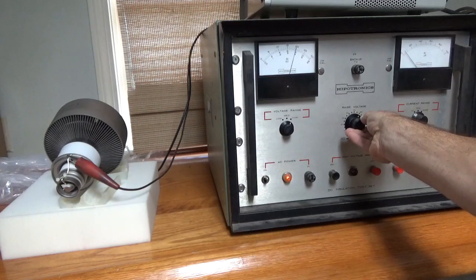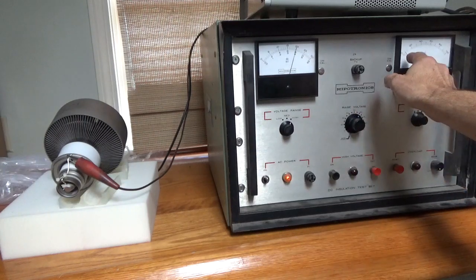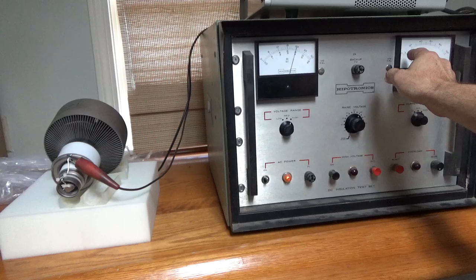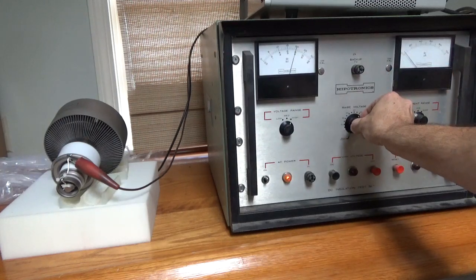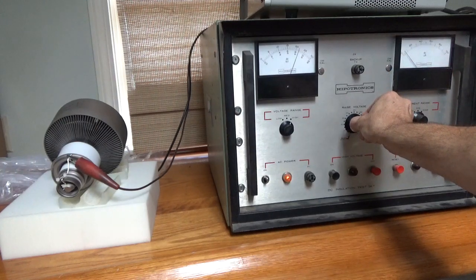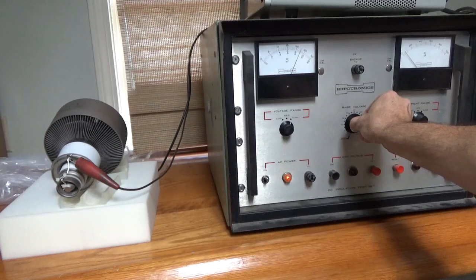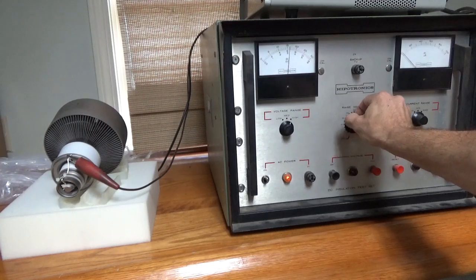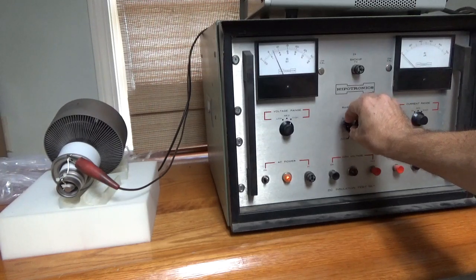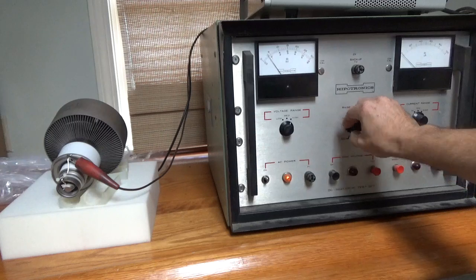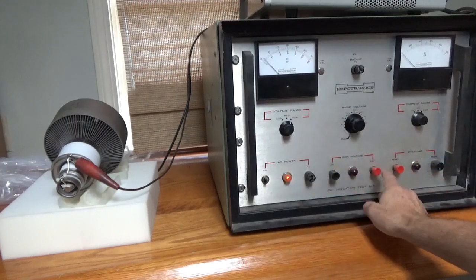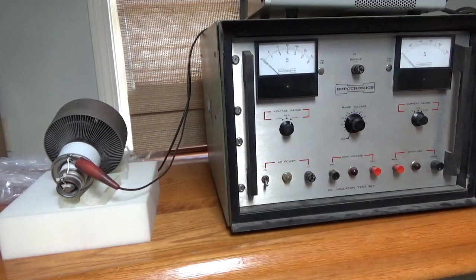Okay, so that's 20 kV DC. That's about three and a half or so micro amps. It can continue to go. So I'm going to back it down. I'm not going to push it. So I'll go ahead and reverse the polarity and repeat the test. I'll be right back.